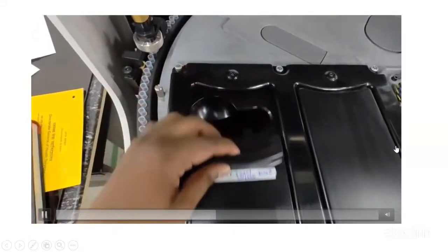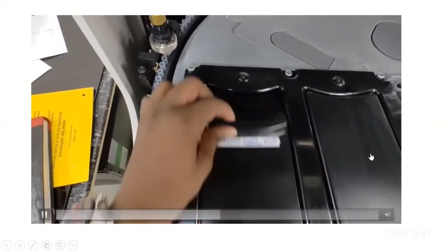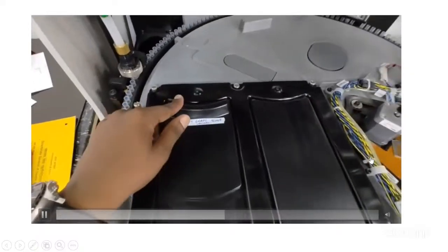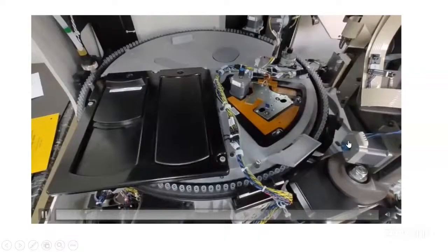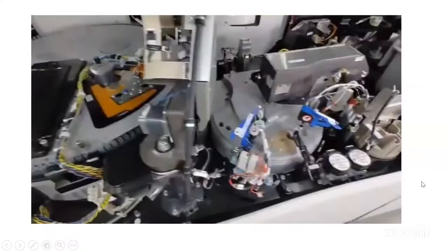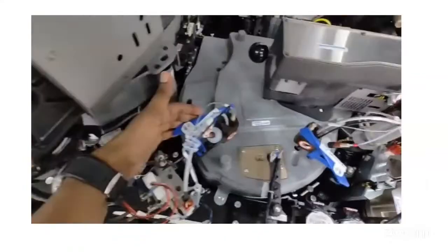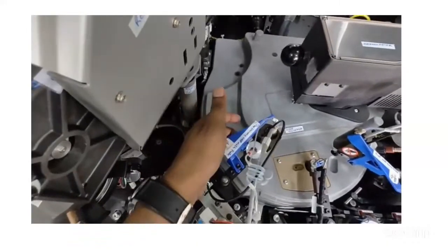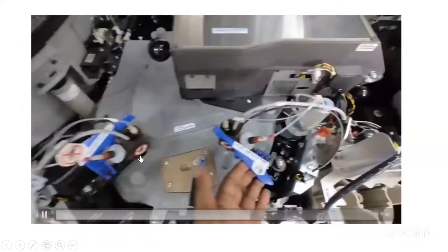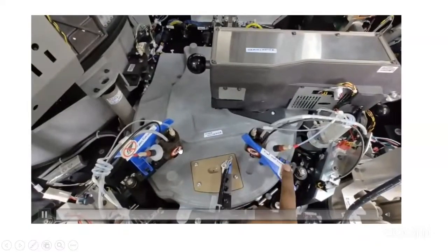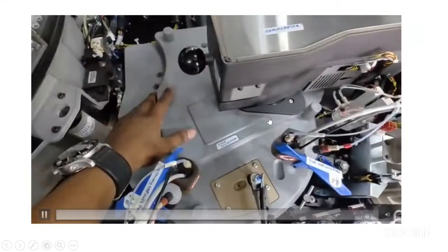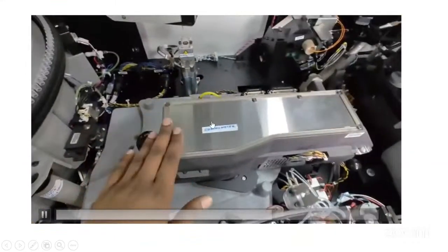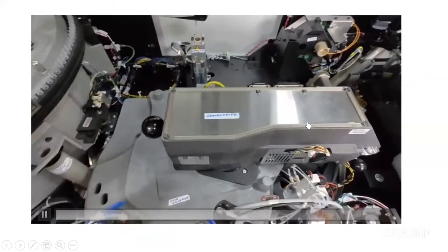For that particular case, you can put a reagent load, and the best part is that for multiple tests you can run, and you can put up to like 8 to 10 reagent loads over here. It's not like that you have to run one particular test type only. If you have hepatitis B, C, you can run. So washing probes for the different washing cycles for the unbound things, and then you have reagents, probes, and this is the incubator, and this is a luminometer for detection.